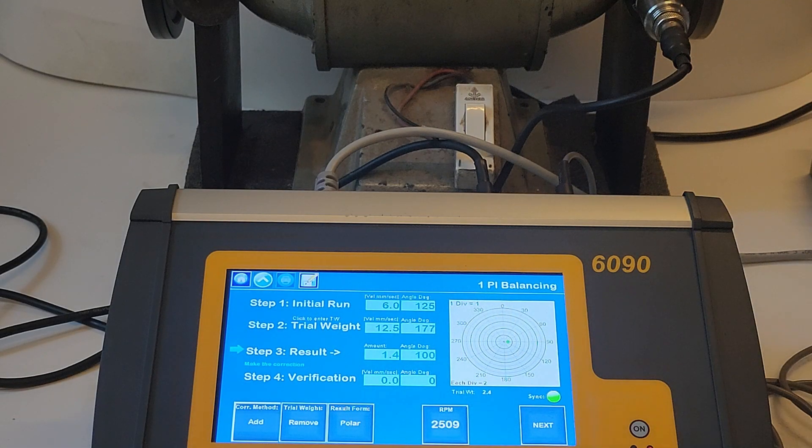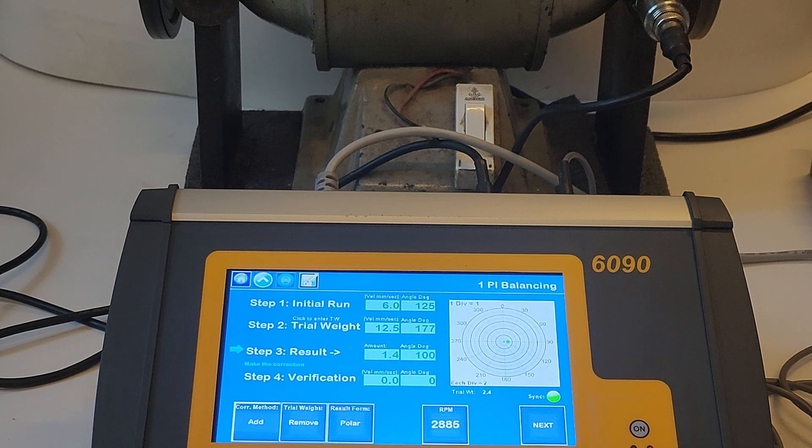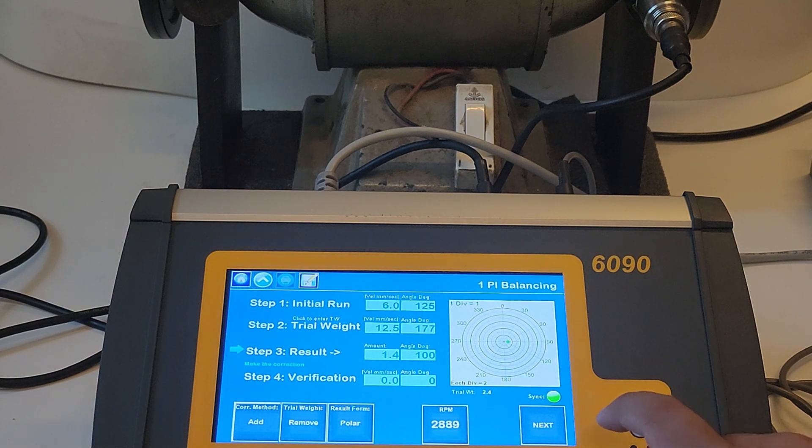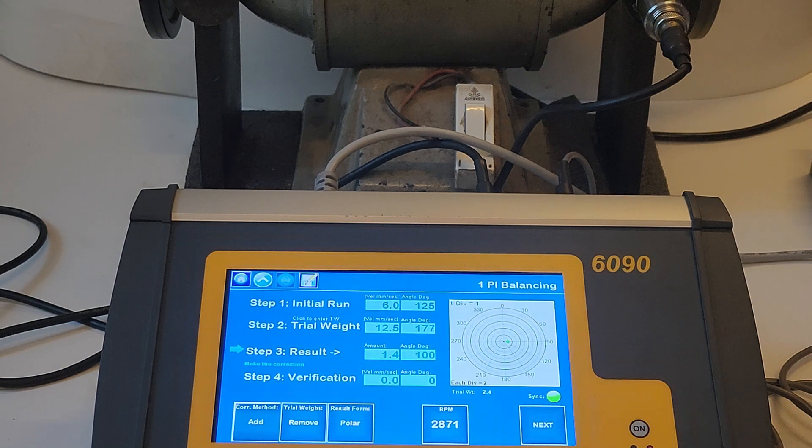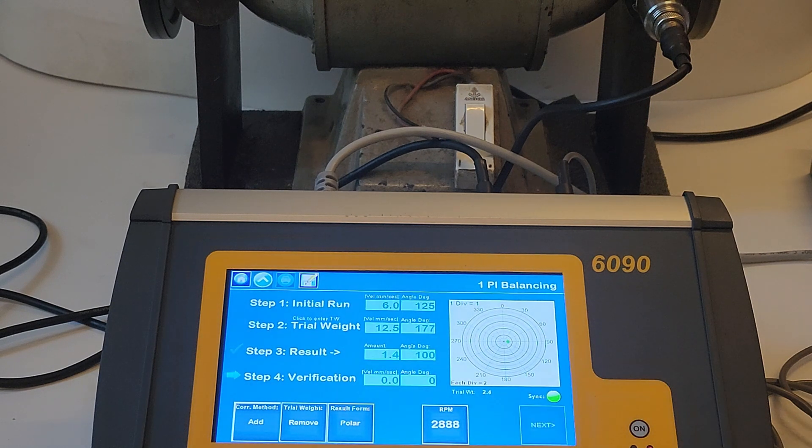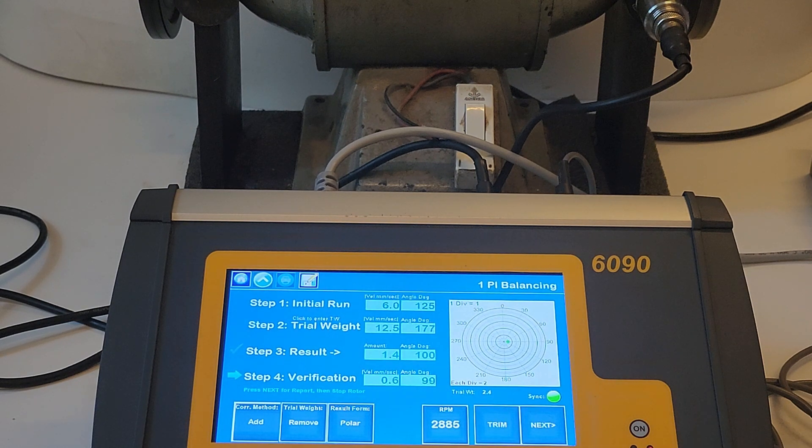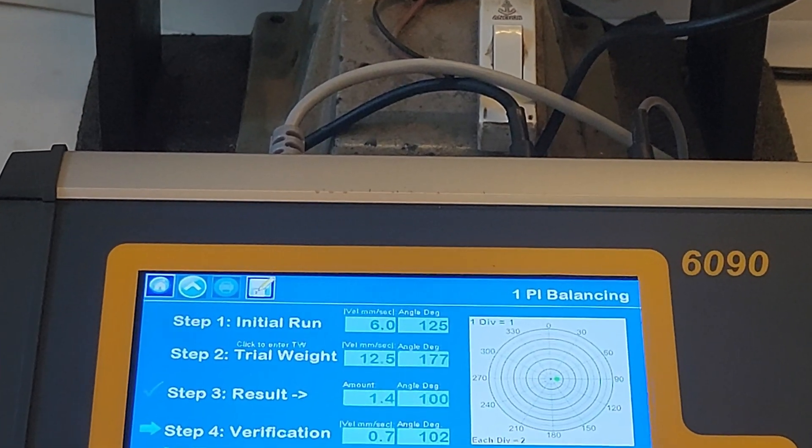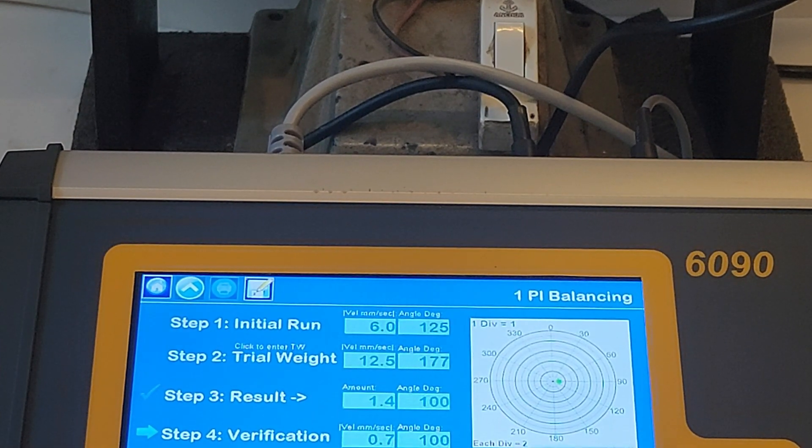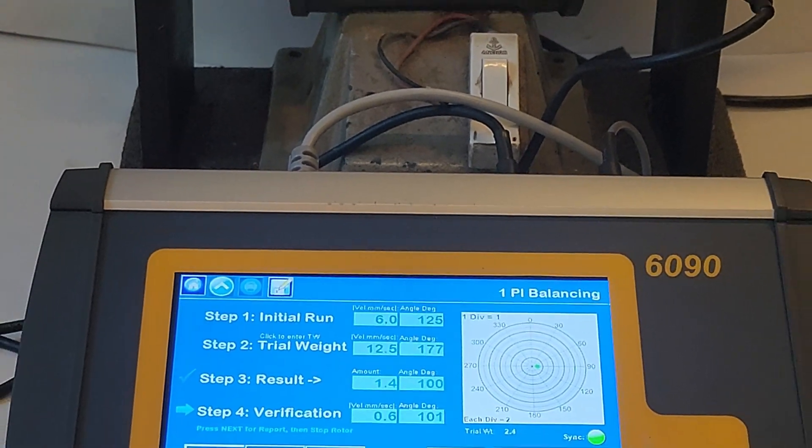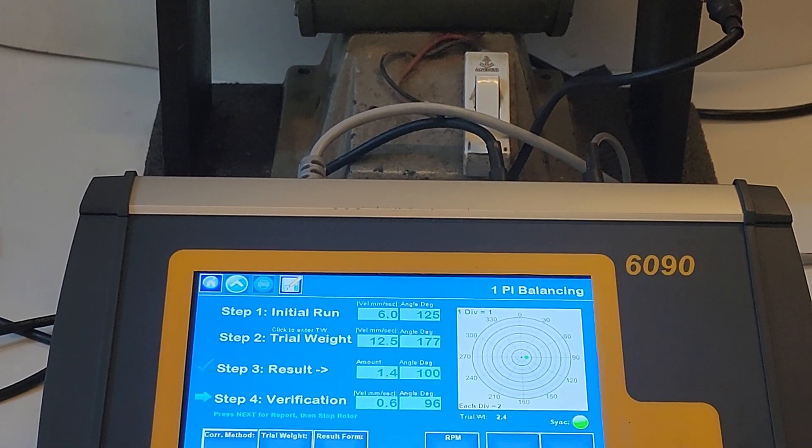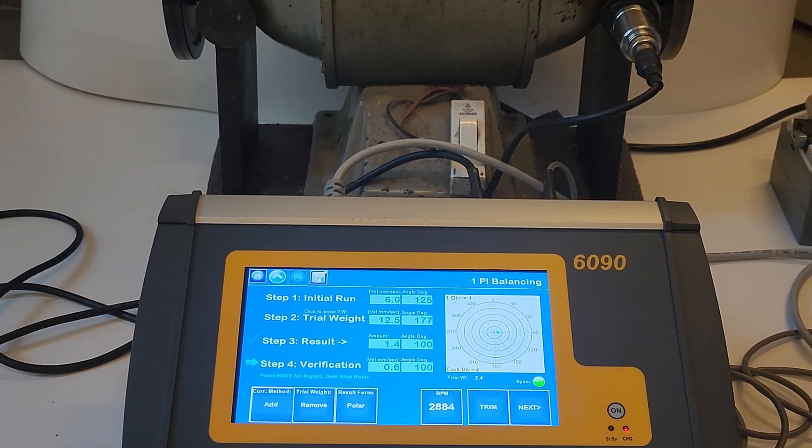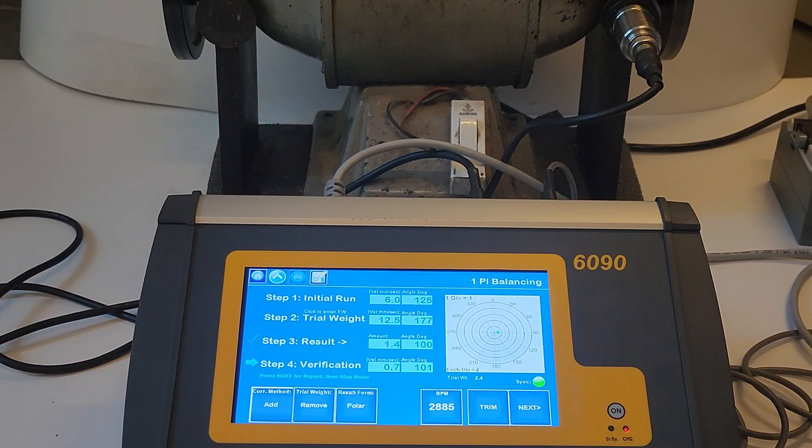After making the correction as per the result, run the rotor again and press next to see the final readings in the verification run. After the verification run, the user has the option to press the trim button to further balance the rotor. However, if satisfied with the final readings, the user can press next to generate the balancing report of the rotor.